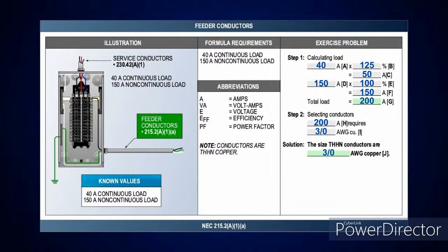Now, feeder conductors. Looky there: 40 amps of continuous load, 150 amps of non-continuous load. If it's continuous, I take it at 125%, so 40 amps times 125% is 50 amps. I have 150 amps of non-continuous, take it at 100%, gives me 150 amps. That's 200 amps. I look at Table 310.16, 75 degrees C column. You need a 3-aught conductor, which is good for 200 amps. Now, did my calculation change at all? No, it didn't change one bit.